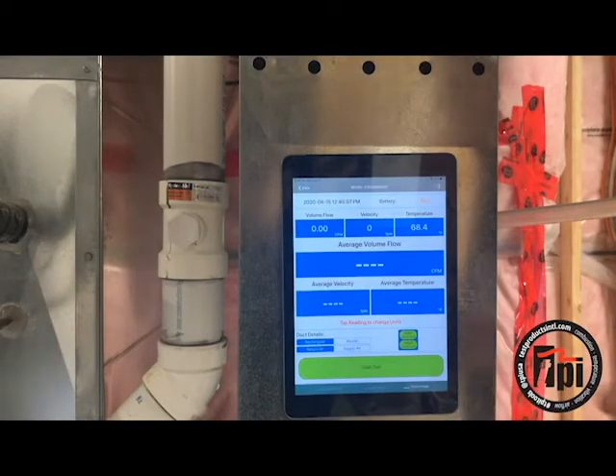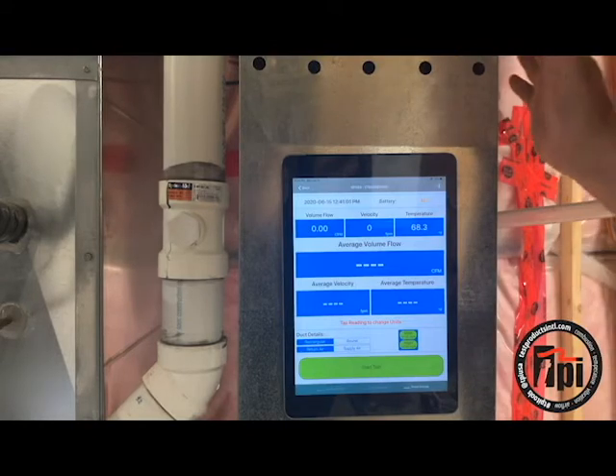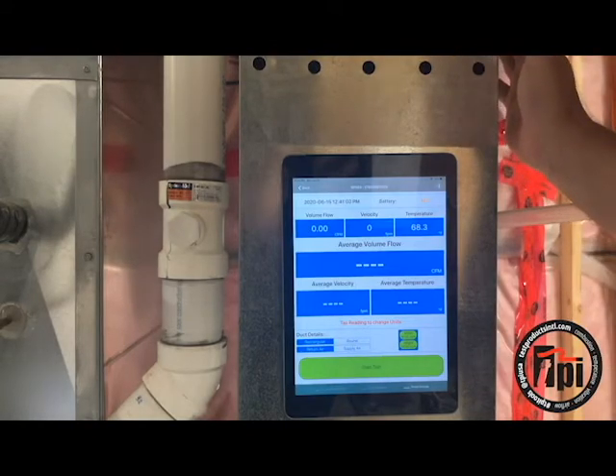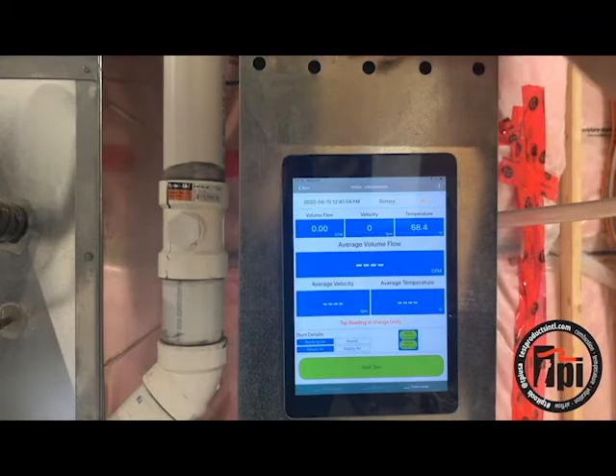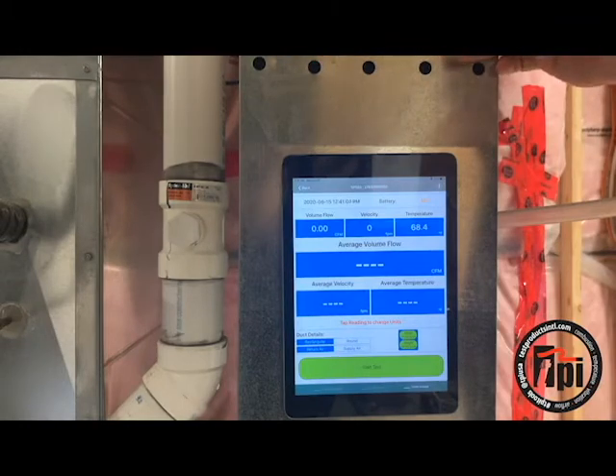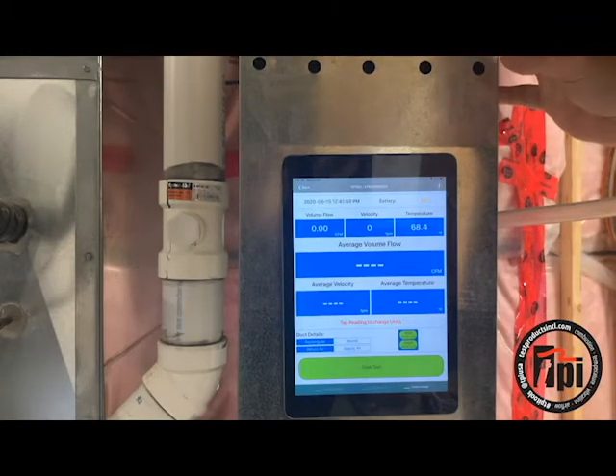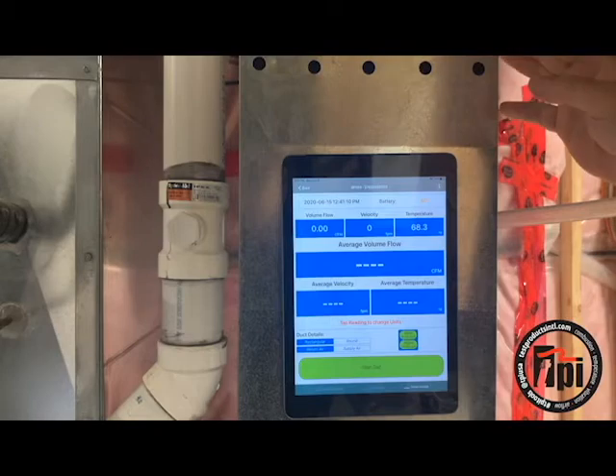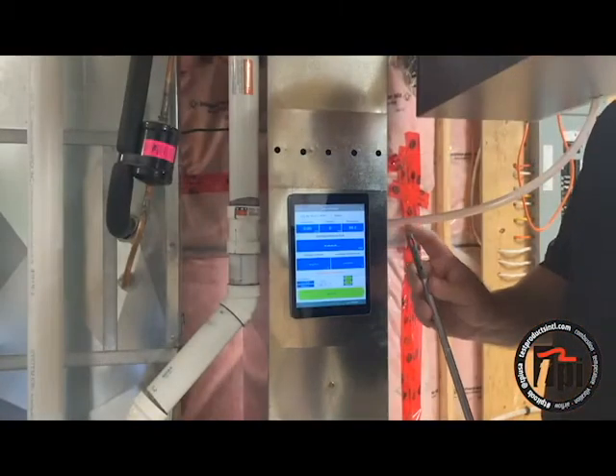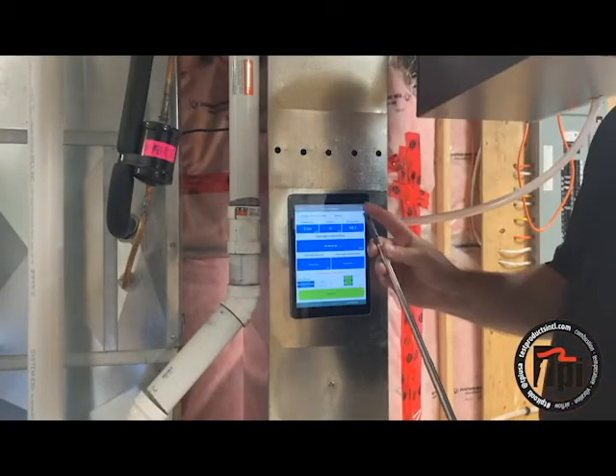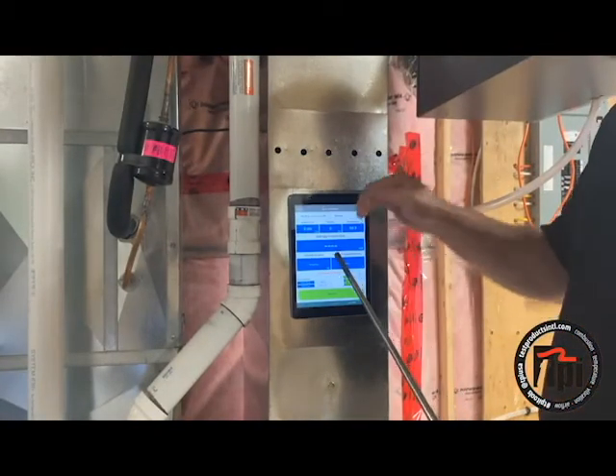The timed average — I like this because you're doing more readings. The more readings on average is going to be a more accurate reading. We've got our five holes here to do our traverse measurements that are drilled in the correct spots. Extend your probe — this is directional, there's an arrow on it that marks the direction of the airflow.